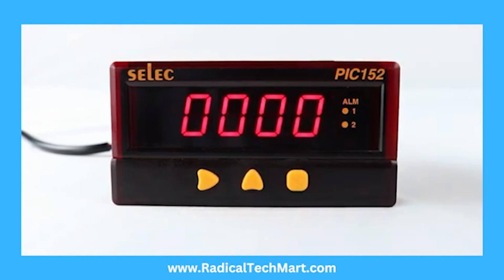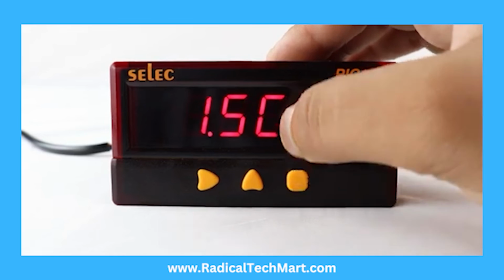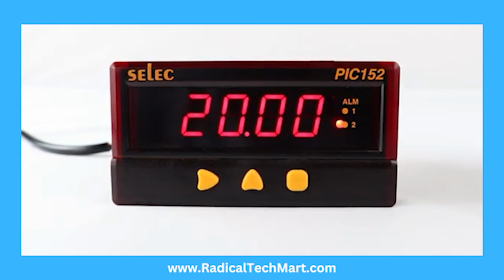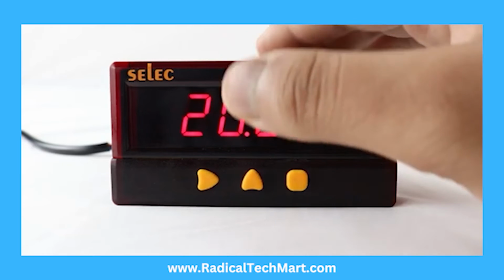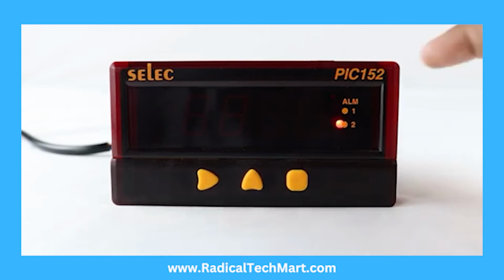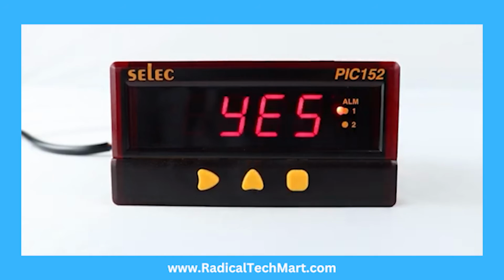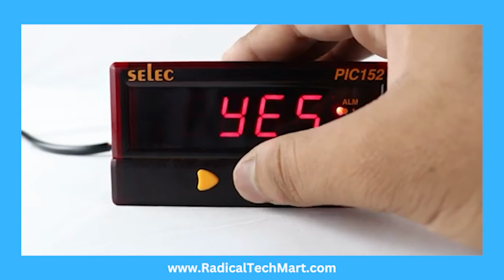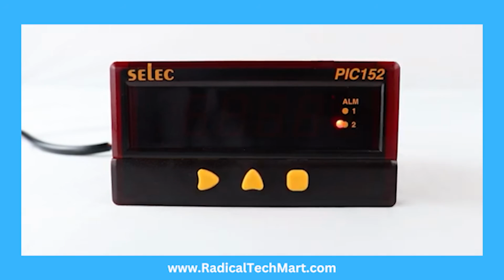Press the square key to set display value scaling point low, DSCL, as 0 by using the up arrow key. Similarly, set input value scaling point low, ISCL, as 0 milliamperes with the help of the up arrow key. Next is display value scaling point high, that is DSCH, as 9999. Next press the square key to select input value scaling point high, ISCH, as 20 milliamperes with the up arrow key. Now, reverse scaling, when selected yes: for 4 milliamperes input, the display will show 9999, and for 20 milliamperes input, the display will show 0.